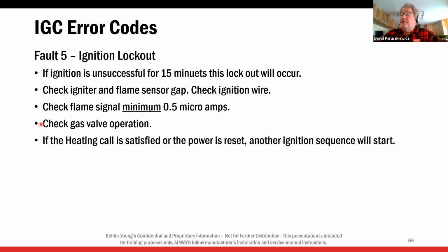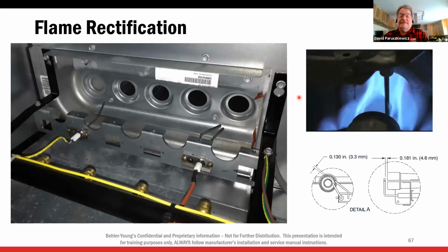Check gas valve operation. Maybe the gas valve's not opening, right? The spark's coming on, but we're not opening the gas valve. So the first thing we should do on this is, is it lighting? If it is lighting, then we've got to look at the flame sensor, or maybe the flame, like I said, is not carrying all the way across. If the heating call is satisfied or power is reset, another ignition sequence will start. So if it locks out, we recycle the power or turn the heating call off, and it'll reset.